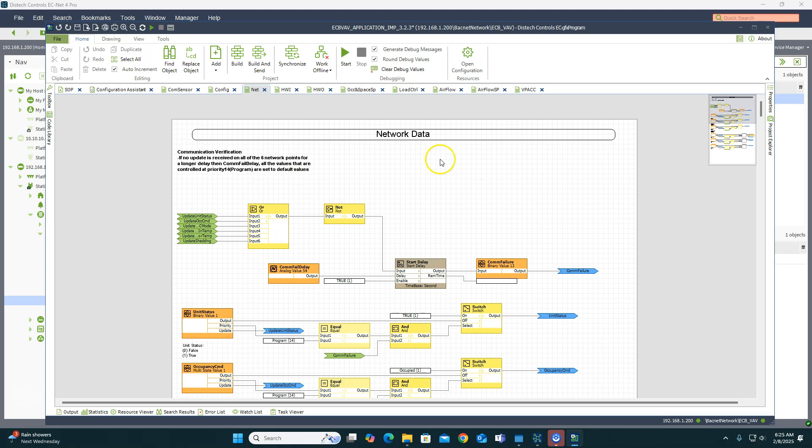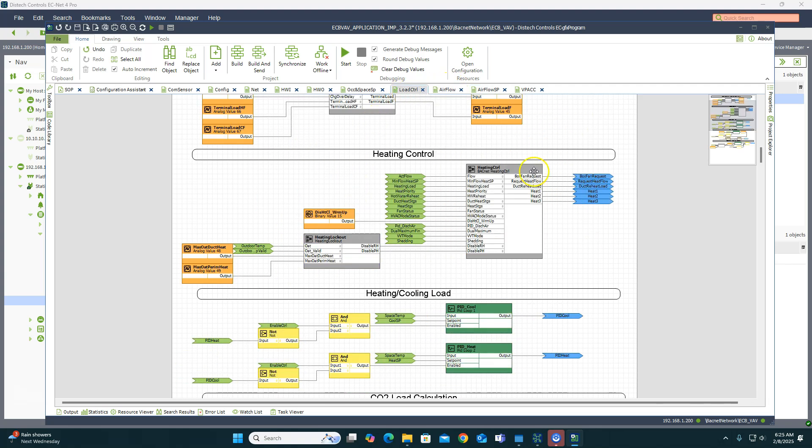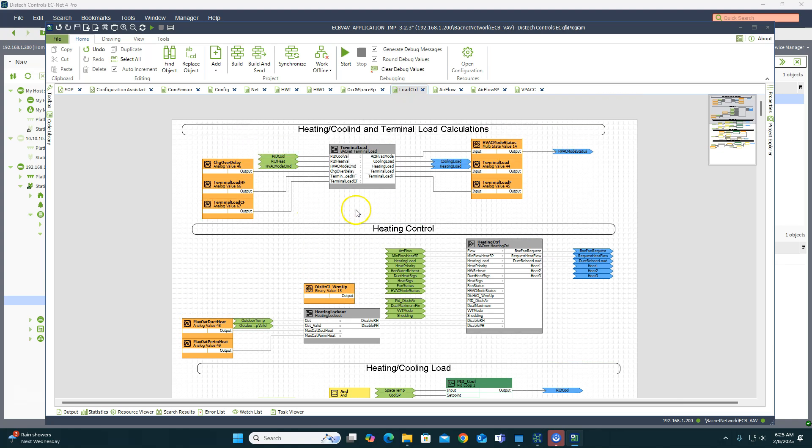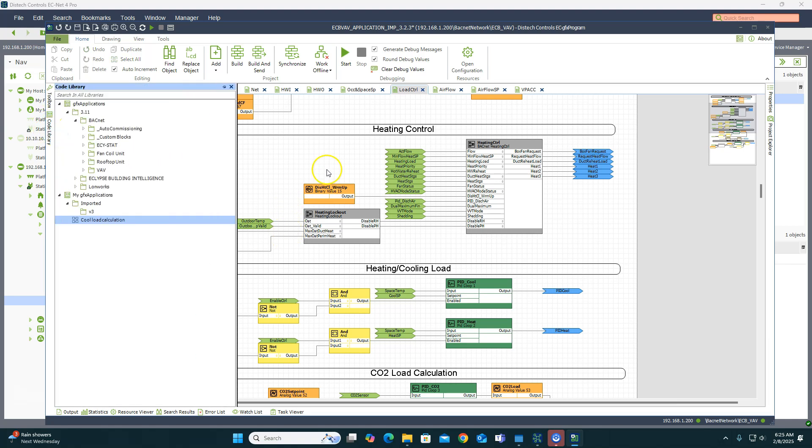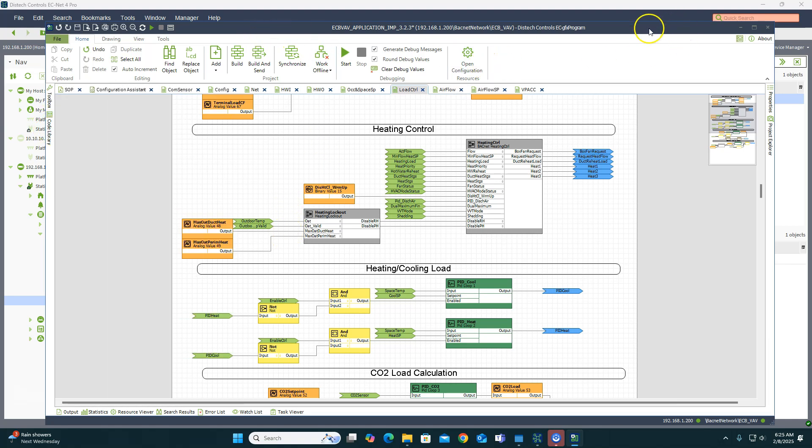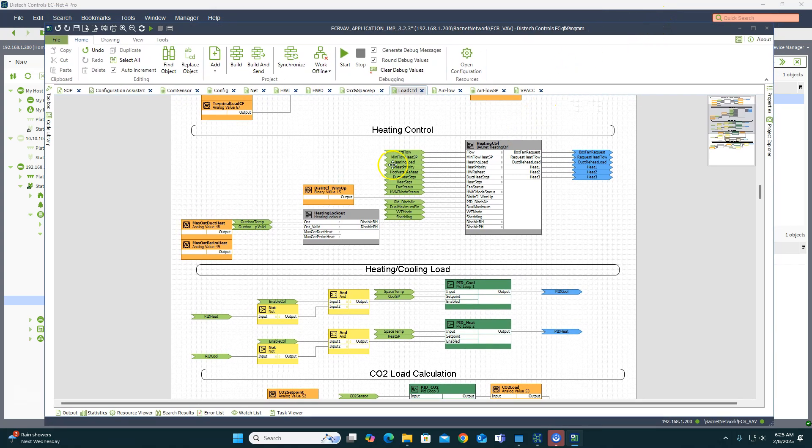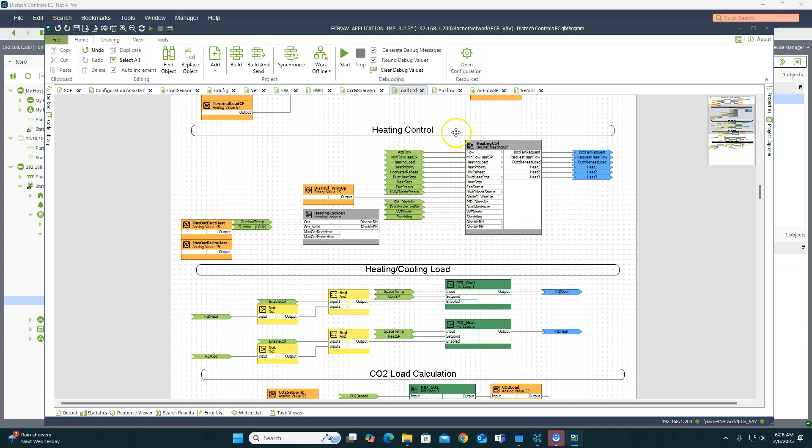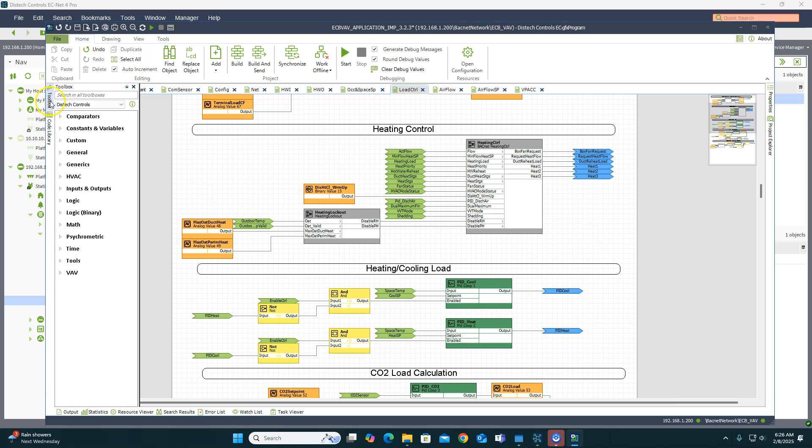So I do like that portion of it. So you can go through the standards and take out what you like, discharge air temperature control. Like you can, we know we can use this in some air handler programming and some other stuff, some CO2 calculations, take out the modular pieces that you need and throw it over here in your code library. And then you can build stuff from scratch. And then you don't have to really worry about this over here where you can't use your inputs and outputs the way you want them to use. So that's kind of a nice thing there to do. Now, just know that now the airflow balancing tool won't work with it. I read that in their documentation. I haven't seen that yet, but there is what they specify as a balancing tool. So if you do your own custom stuff, none of that will work. But overall, I do like it. And if this looks similar, and if you've been doing Johnson for a while, well, all of Johnson's LON stuff is DisTech. It's just rebranded Johnson. So if you've ever dealt with the LN controller or LX controller, that's a DisTech controller. And that's this programming right here. It's just Johnson relabels it under their name. They buy that from DisTech to do that with.